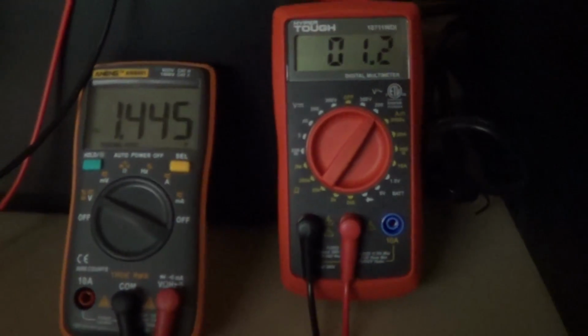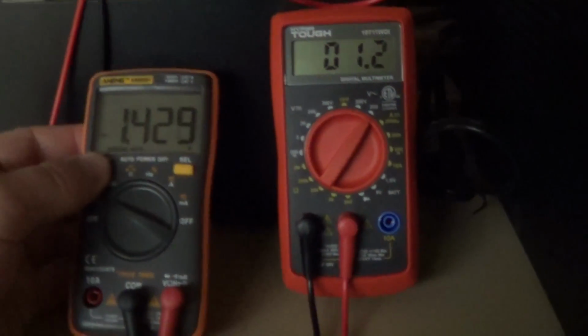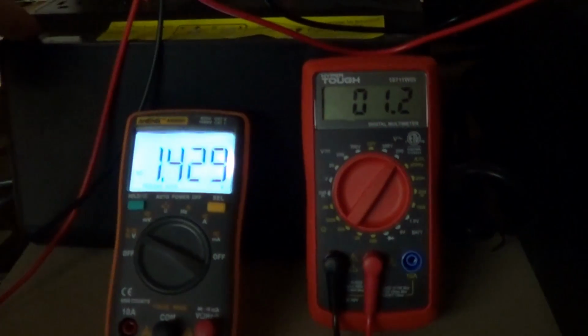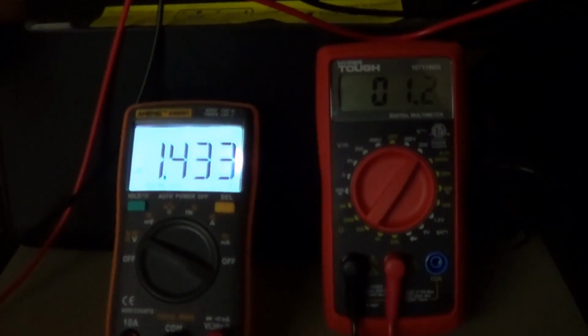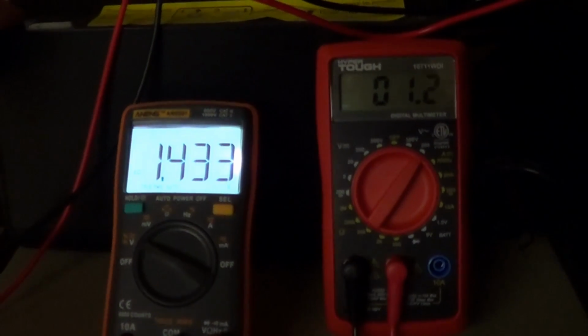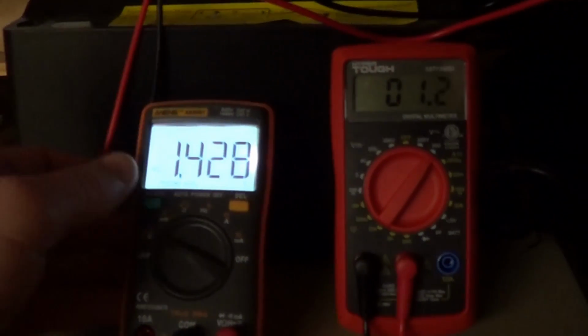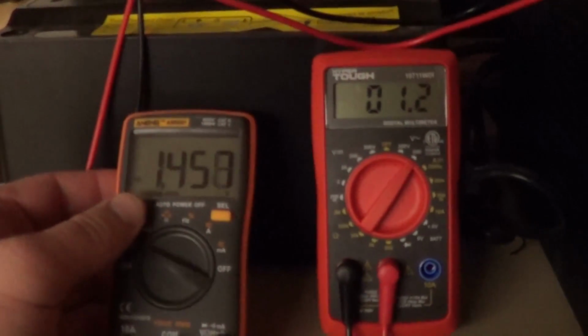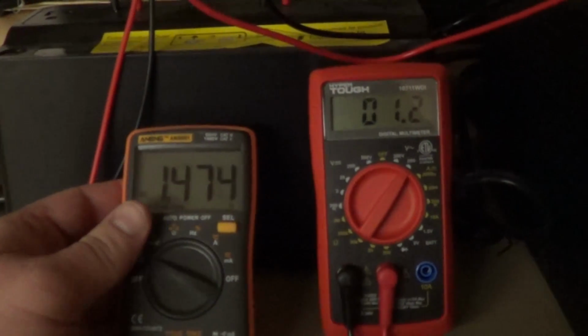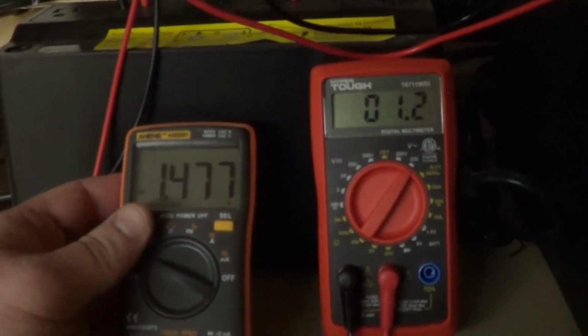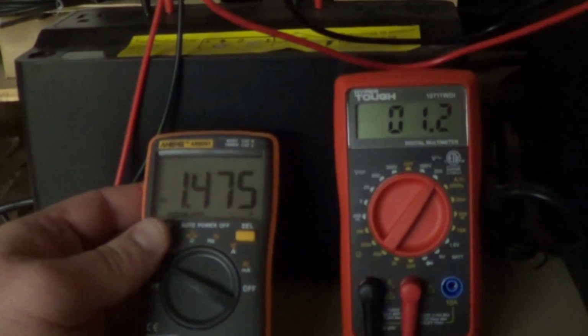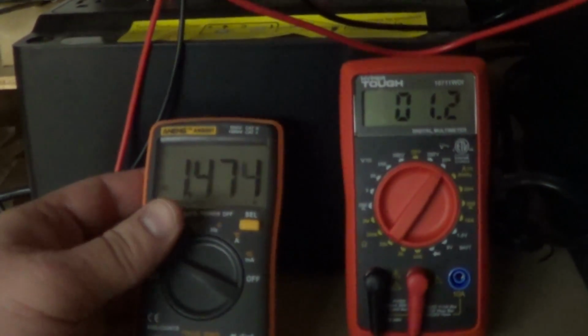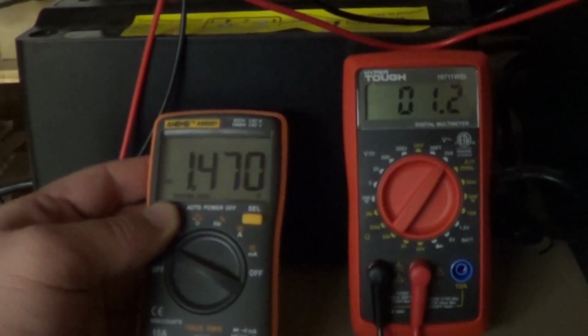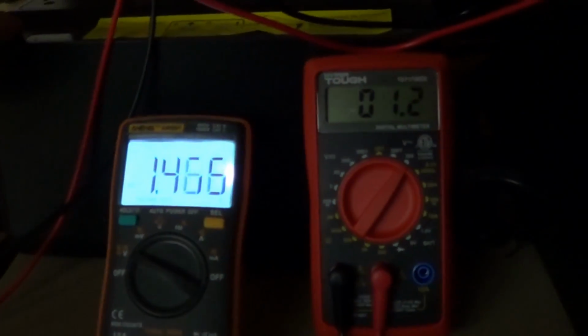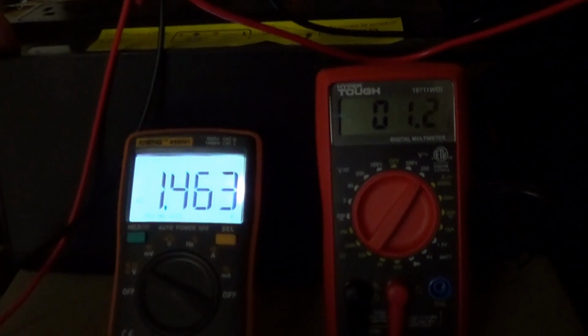When I turn this uninterruptible power supply on, at first it will be on the AC power line, and both meters will read very similarly and correctly. But then it will perform a self-test, and its inverter switches over to power the built-in outlets, outputting what they call a simulated sine wave, or stepped approximation to a sine wave—actually a square wave signal with periodic drops to zero level before it transitions and changes polarity. So first we'll see the line voltage.